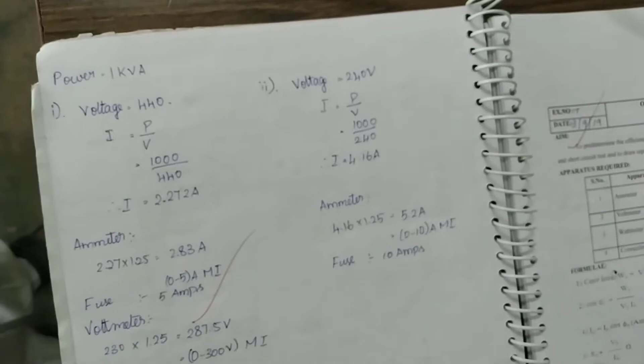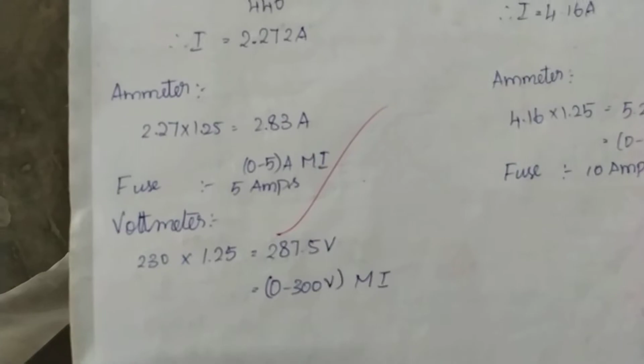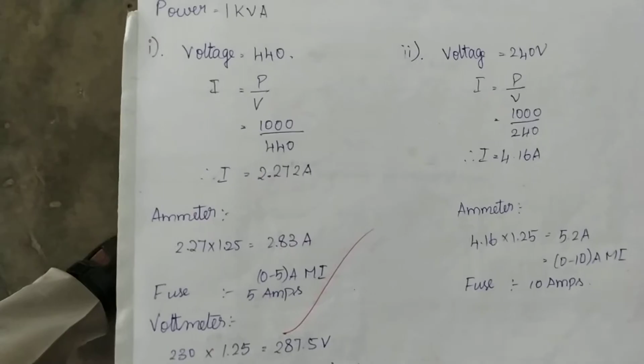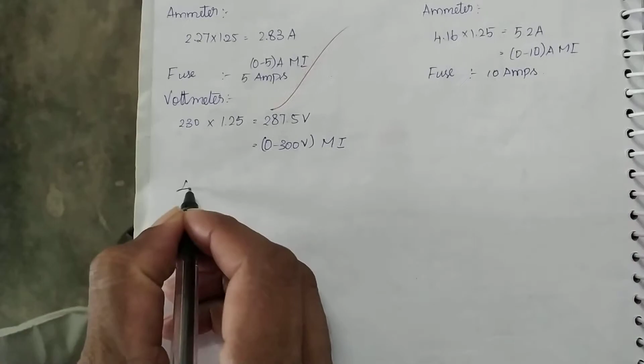Right, so for the voltmeter, normally you have to use 0 to 150 because you are performing the short circuit test at a very minimum voltage. Normally you can circulate the rated current. That is why we are using 0 to 150. So for the voltmeter, our high voltage is 440 volt, and we are using 0.25 of it.